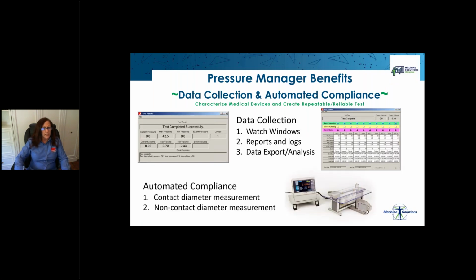Data collection and automated compliance. Pressure Manager offers a lot of watch windows. There are reports and logs, and it allows us to export the data for further analysis. Some of the watch windows you can see here on the right: we have the smart manifold watch window.